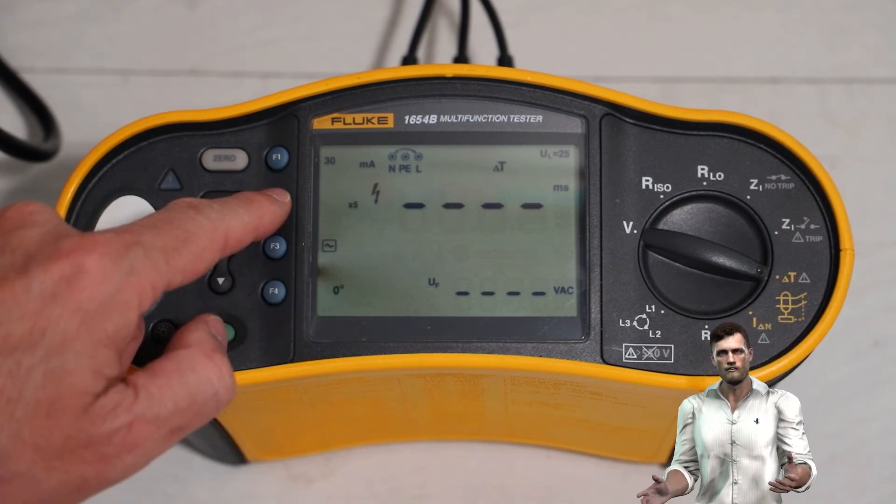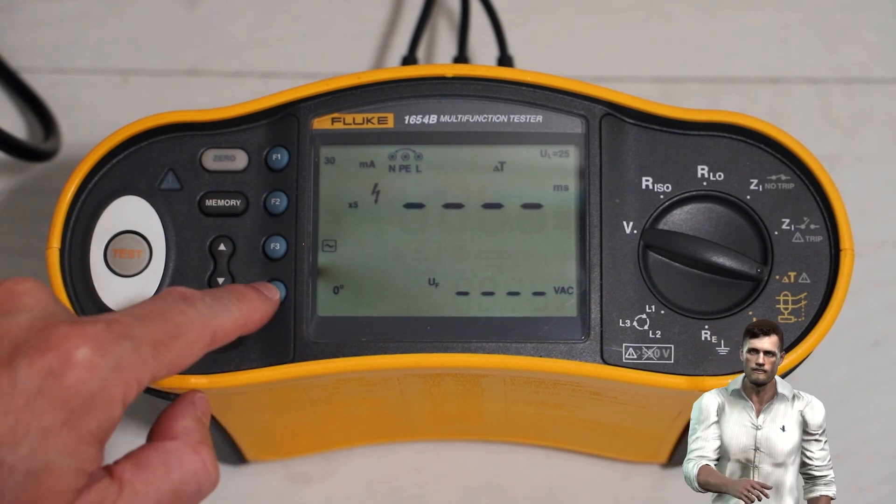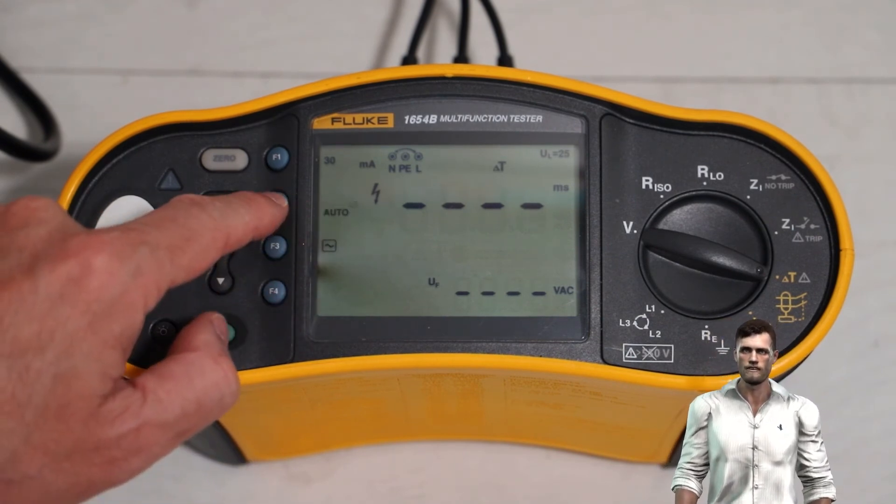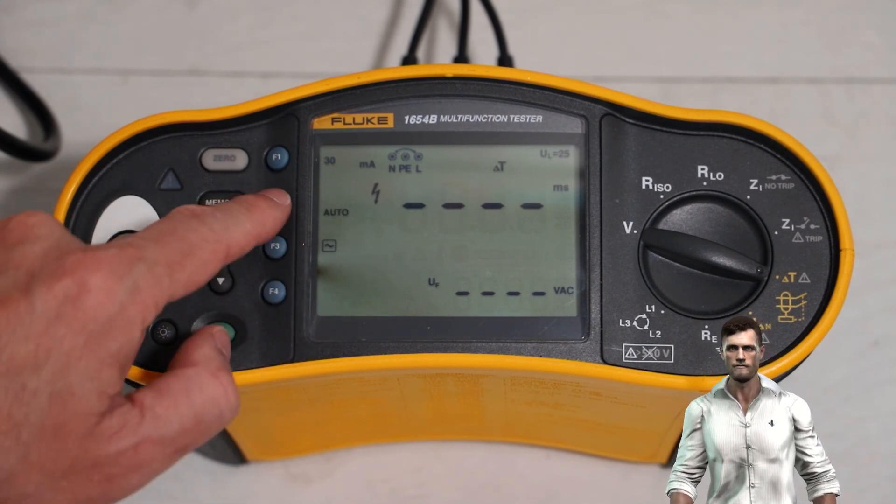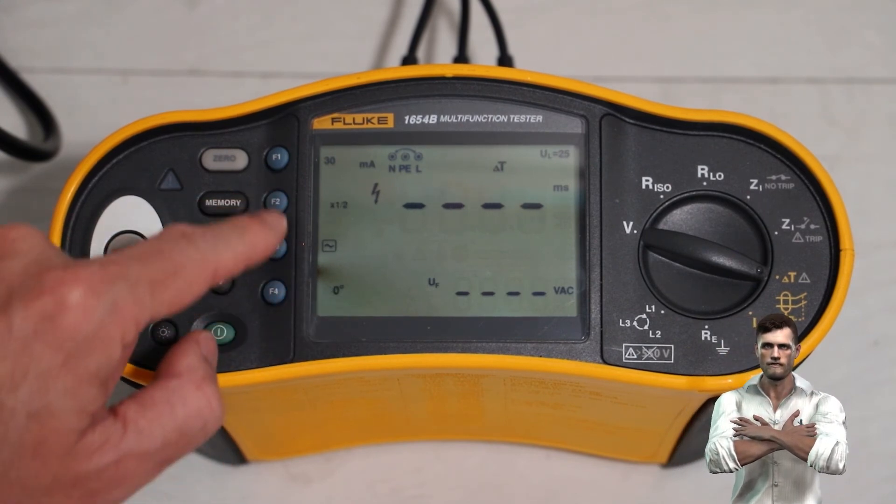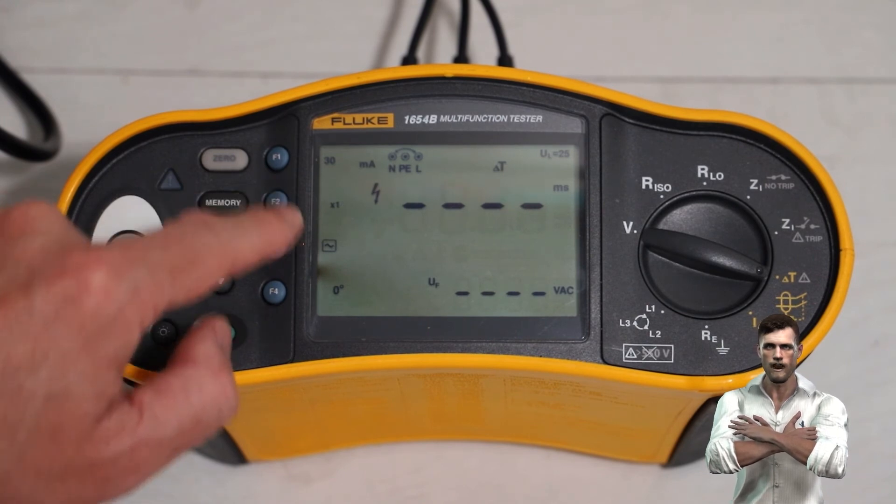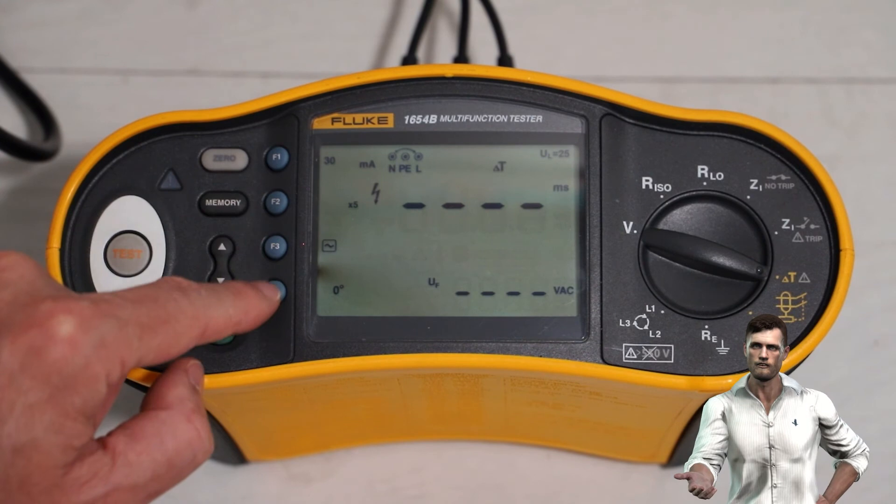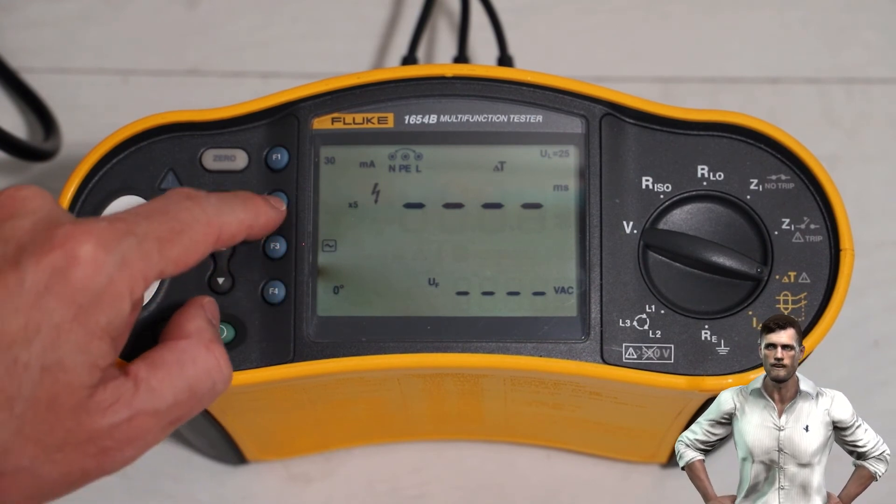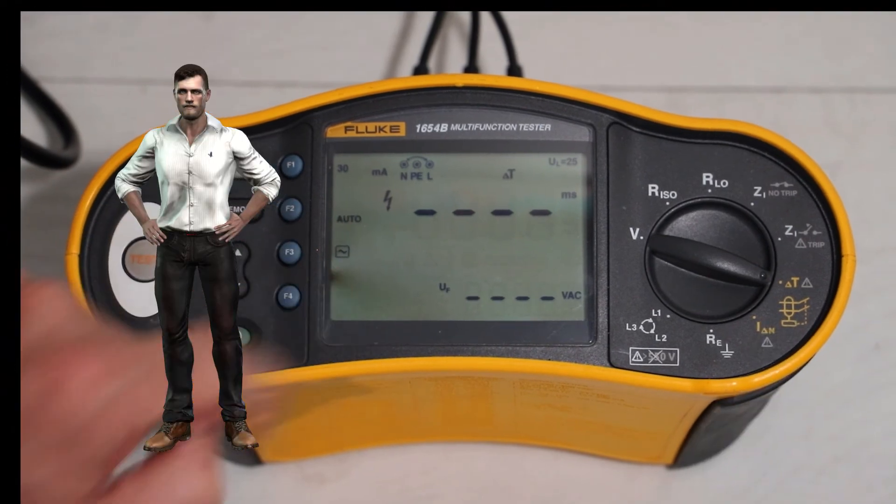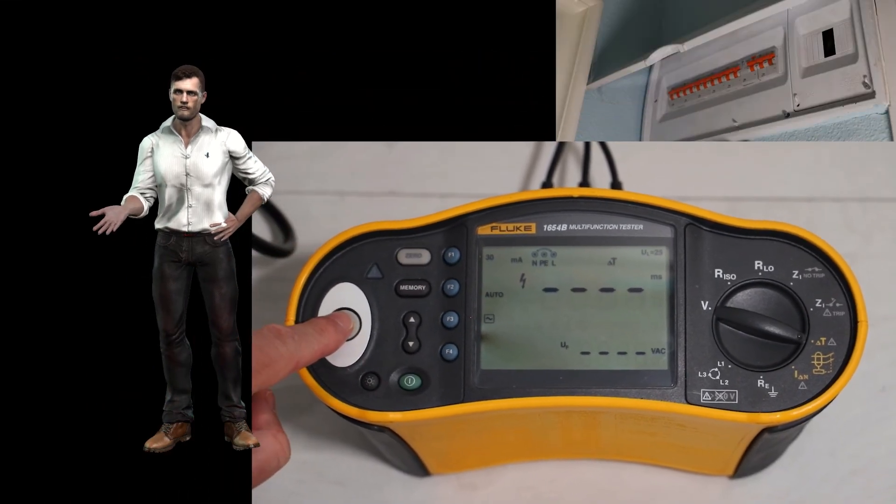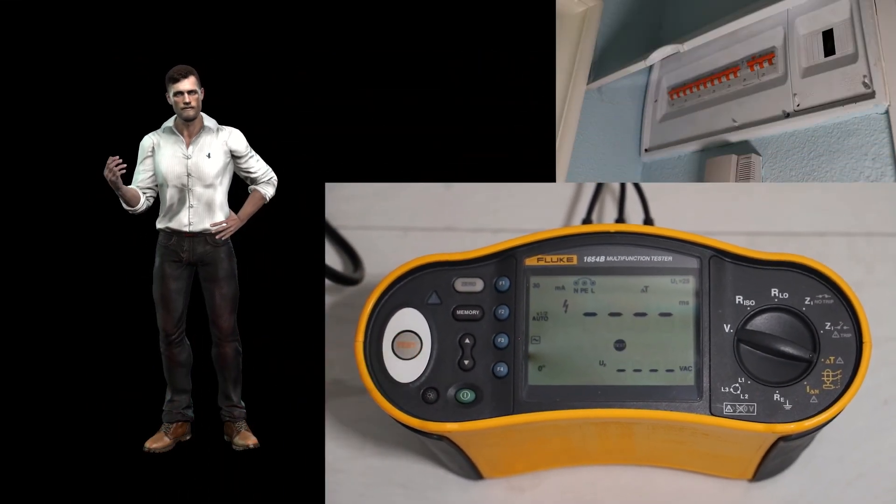Finally, with the F4 key, we could select between two options, 0 degrees or 180 degrees, in order to select if the test is done with the positive or negative cycle of the voltage waveform, but in this case, as I have selected the auto mode with the F2 key, then the instrument will perform the test sequentially with both the positive and negative cycle of the waveform. Now that we have configured the instrument, we can press the test button to start the differential protection verification process sequentially.